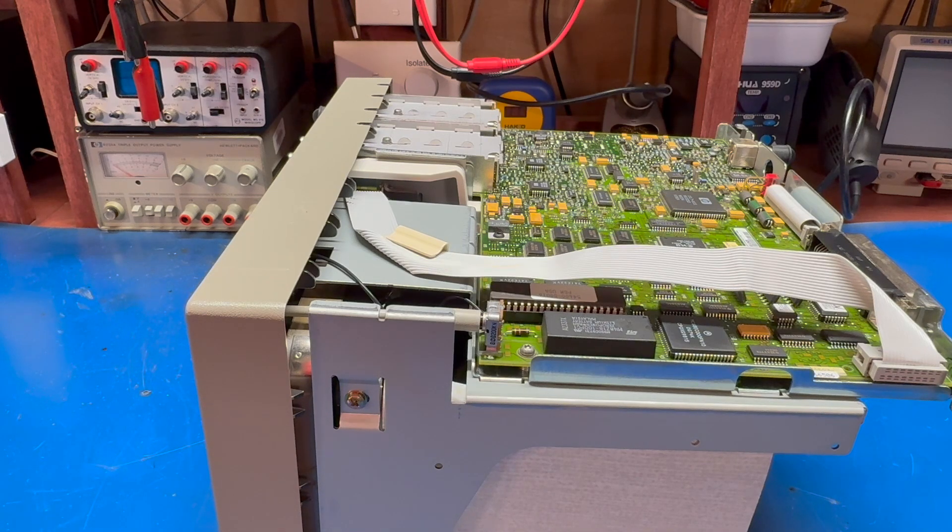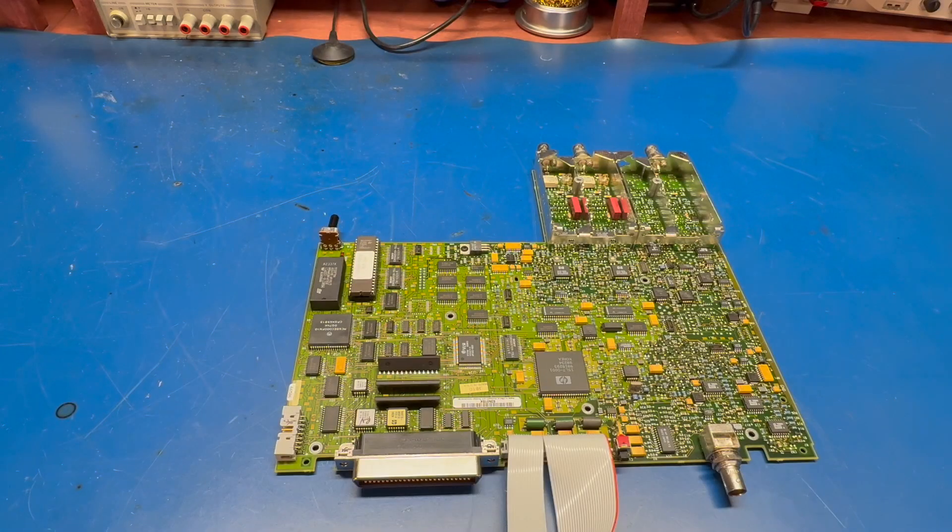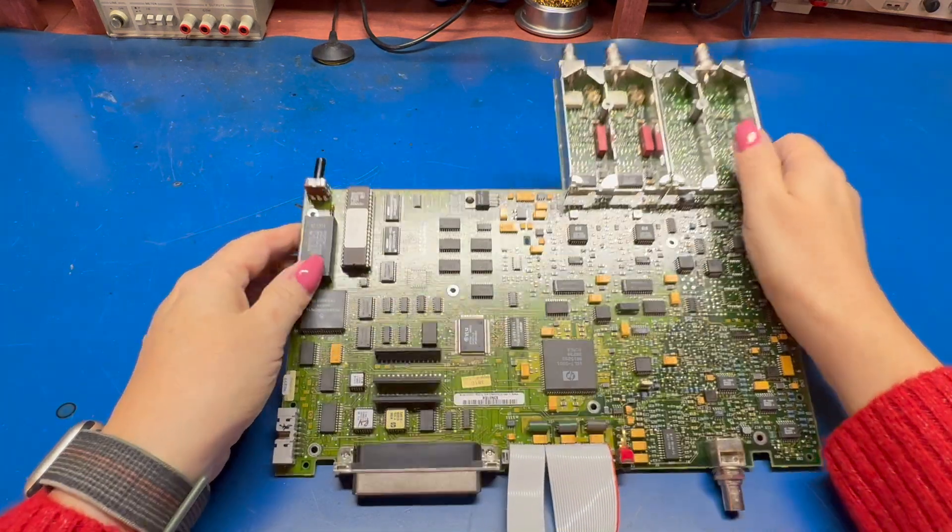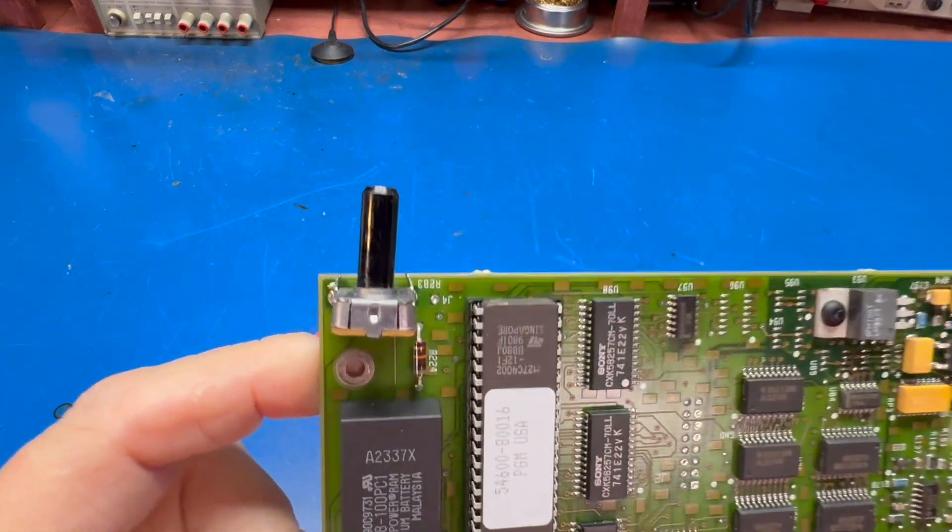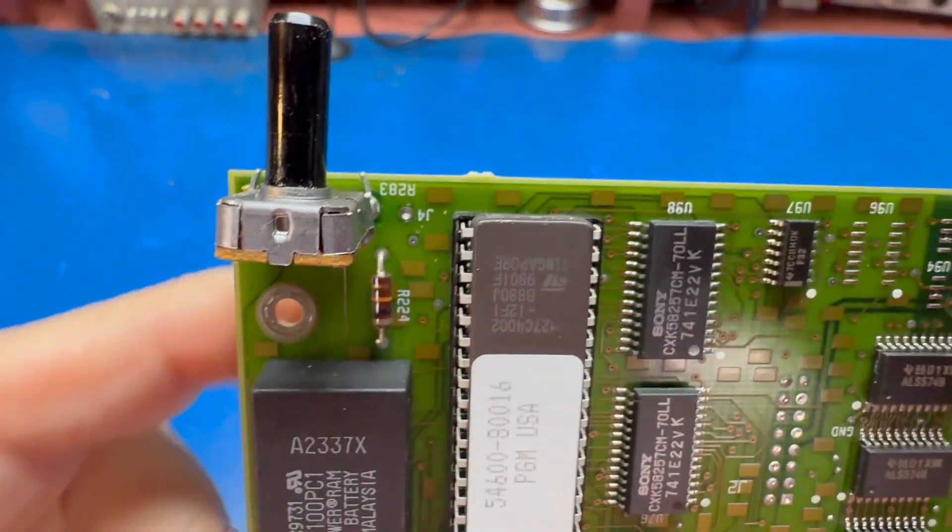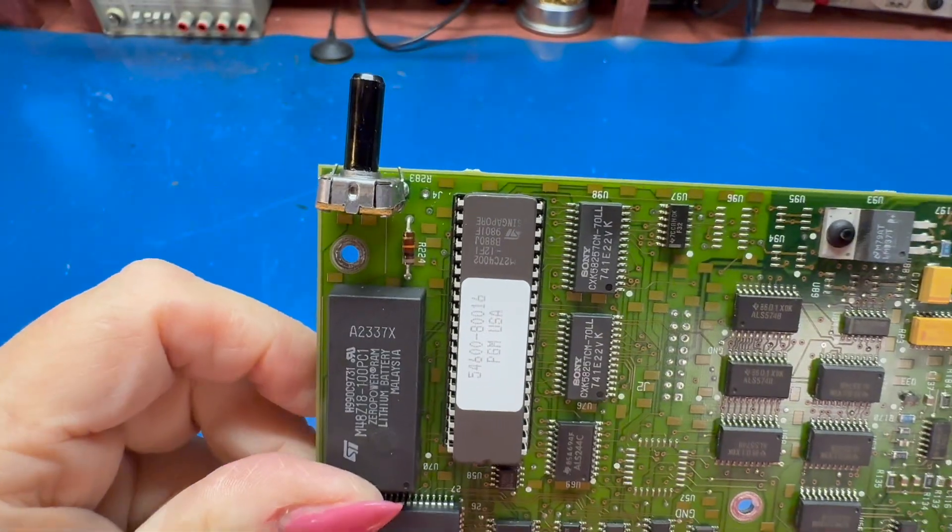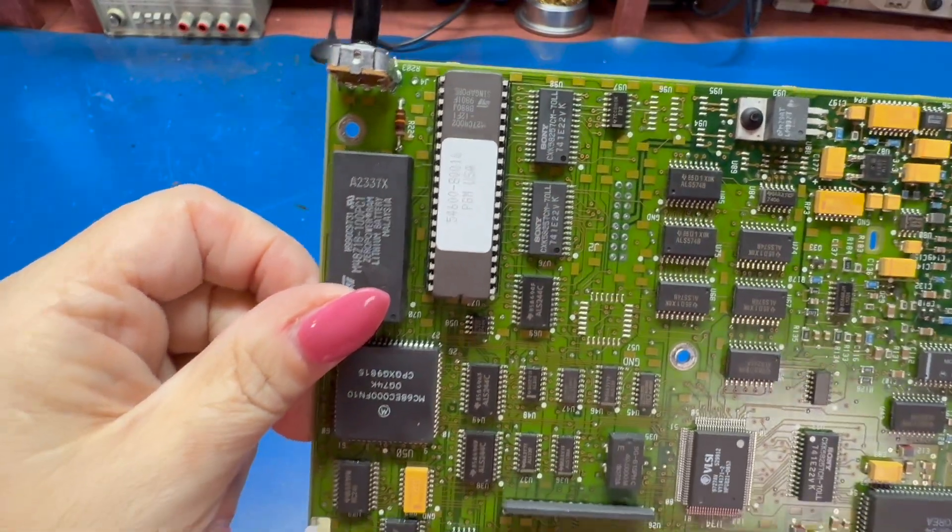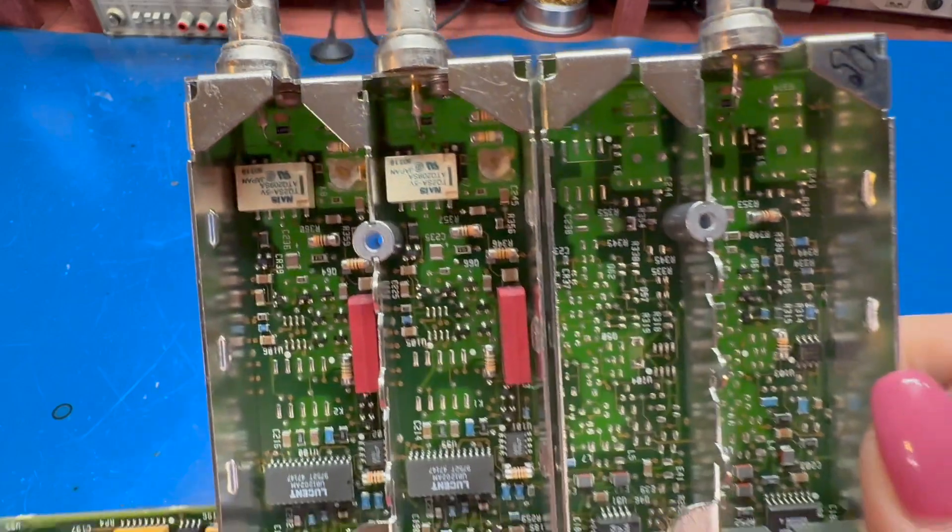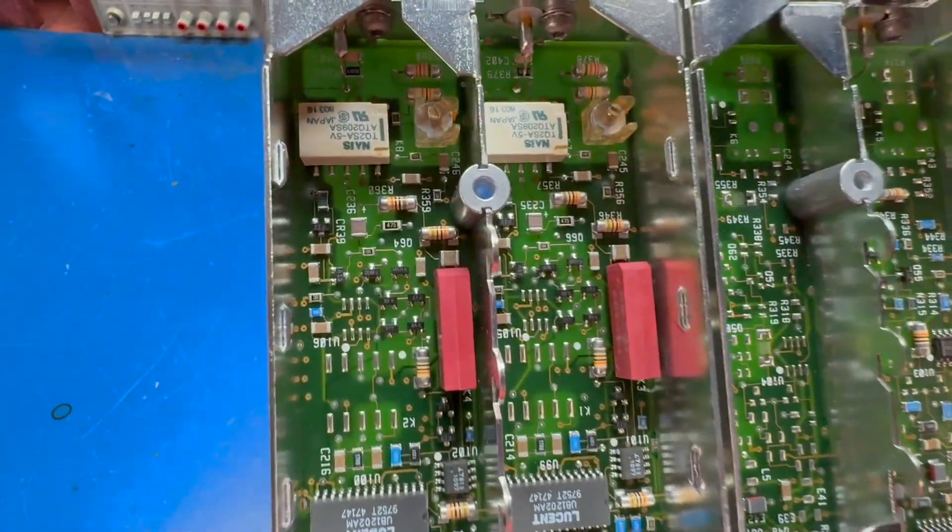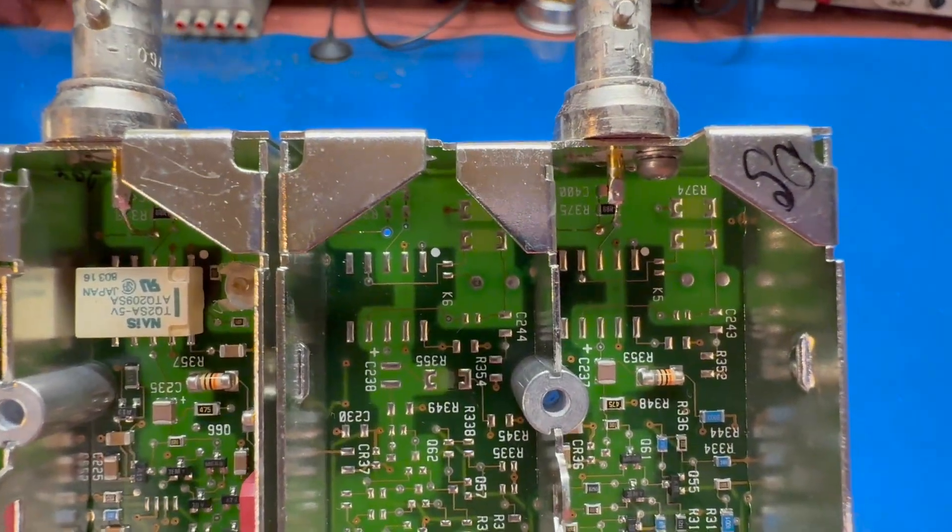All right, we've got the main board out. Actually came out pretty easily. I did have to unsolder one small wire at J4, that was to the probe calibration piece at the front of the scope, but otherwise everything came out. Here's our front end, here's channels one and two, and here's the triggering section.